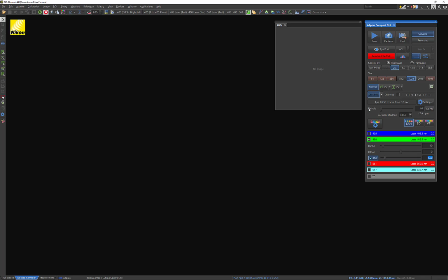And this is a setting that's actually integral to confocal microscopy, because of course confocal microscopy is only possible by employing a pinhole. The pinhole is there to reject out-of-focus light so you can get very crisp-looking images. By increasing the pinhole size, you allow more light in, but you also allow more out-of-focus light. So you might get a brighter signal, but it's going to be less resolved than if you used a smaller pinhole size. You can choose to increase this above what's already calculated for a specific wavelength and objective, but I would honestly say it's probably better to keep this at whatever the suggested value is.